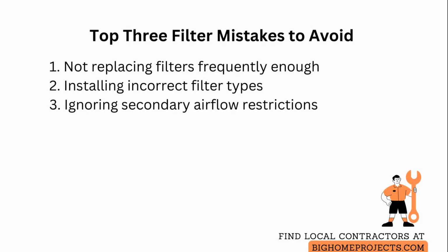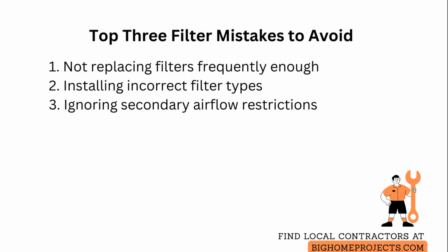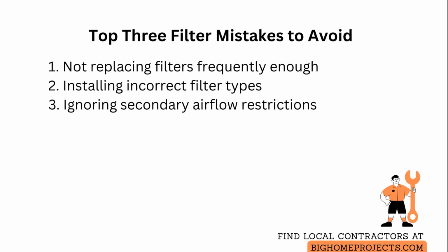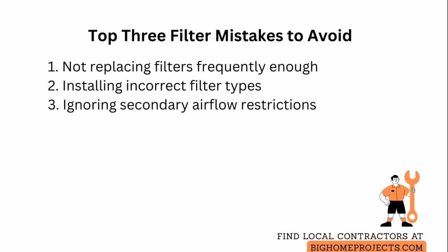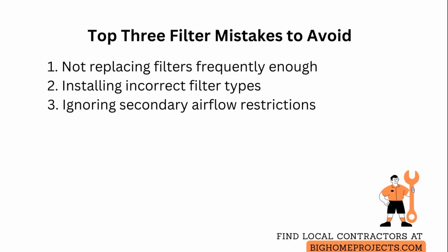When ducts, grills, or dampers are restricted, remove visible obstructions. Check that dampers are set fully open, and trace the duct run for kinks or crushed sections that need repair.